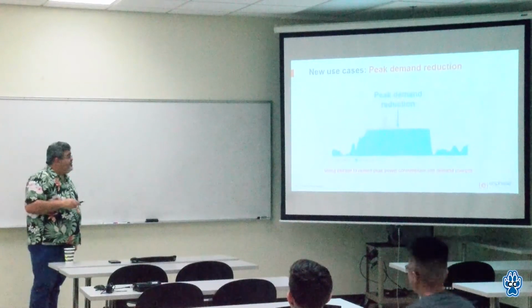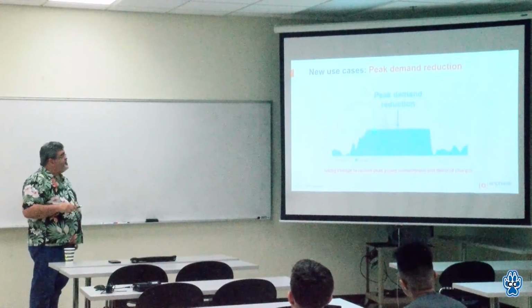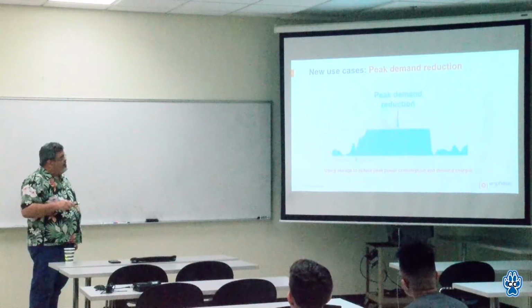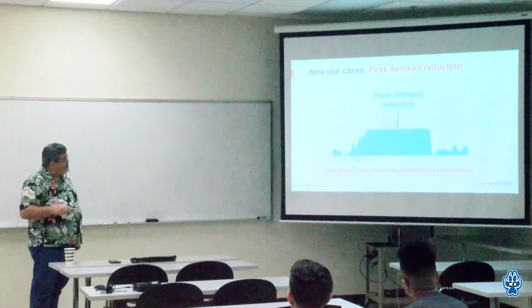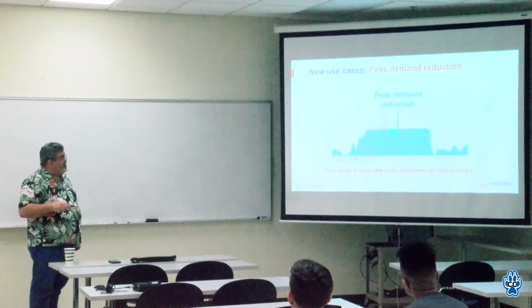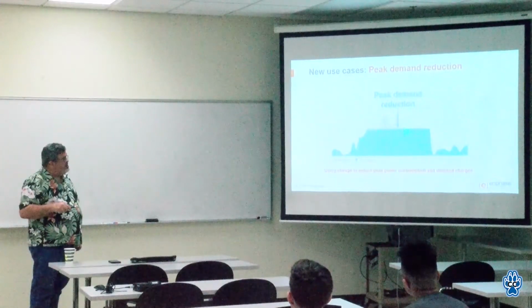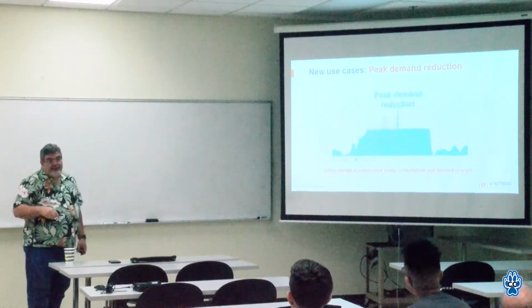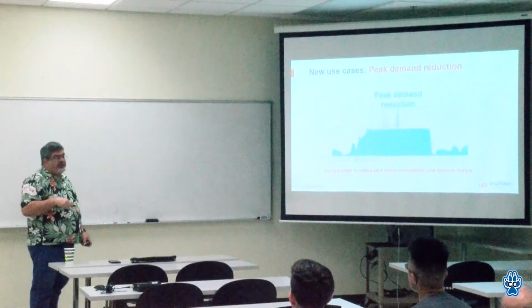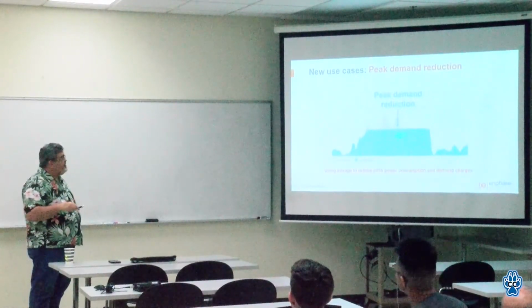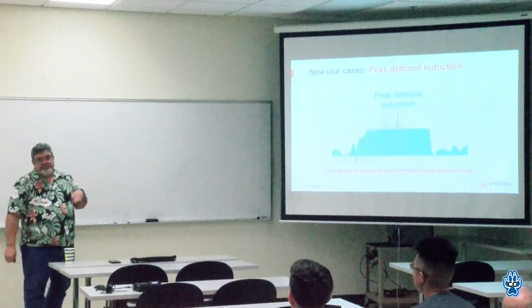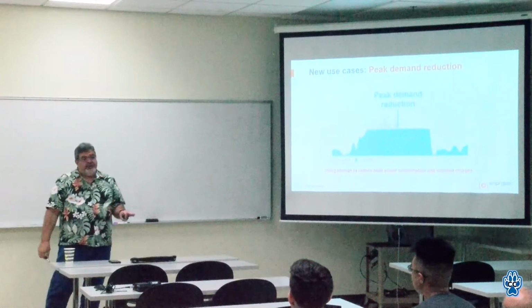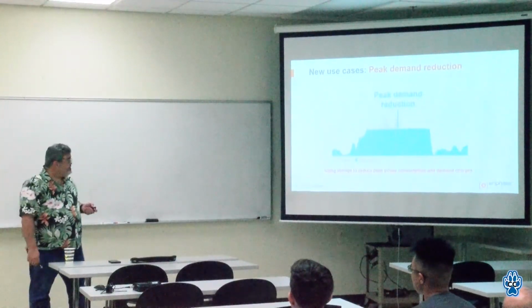And that's what his rate for the entire day is going to be based on, that peak. This is where storage can really help, because now I can discharge my batteries during that time, lowering my peak to this new level. Then I can charge off the grid the rest of the time. So this is peak demand reduction, reducing the total cost of your energy for the day.